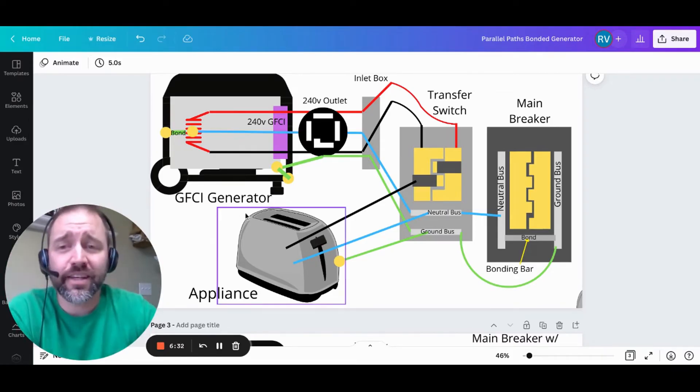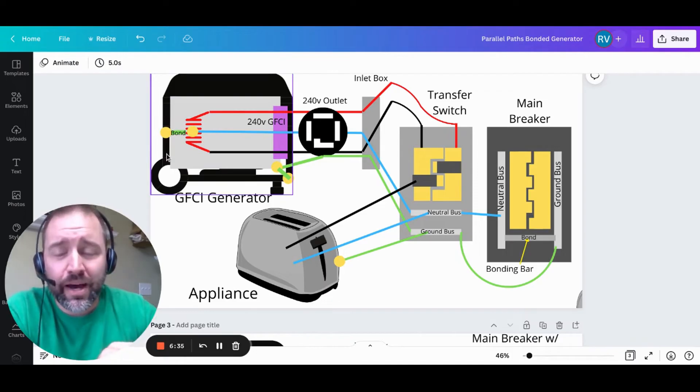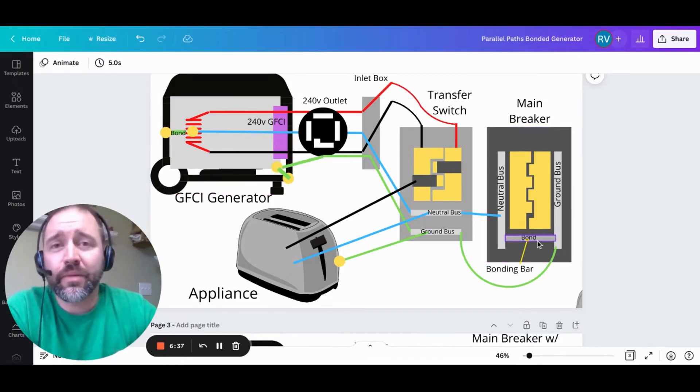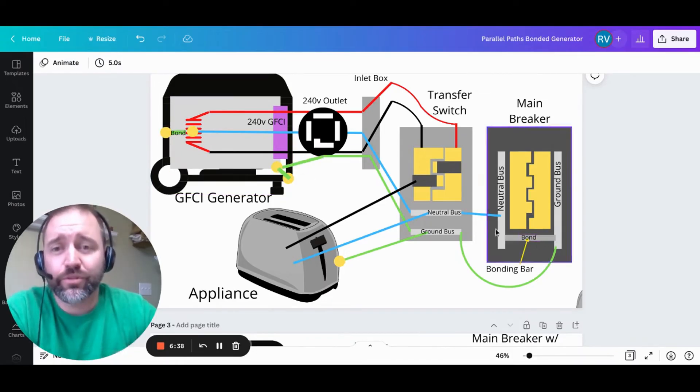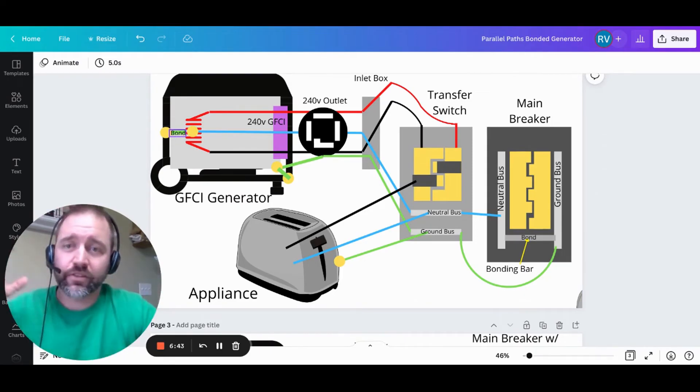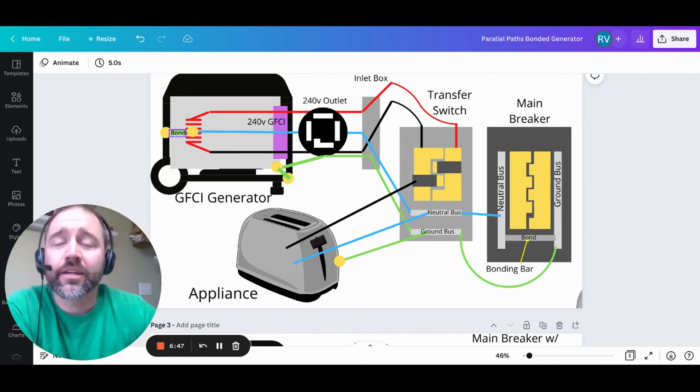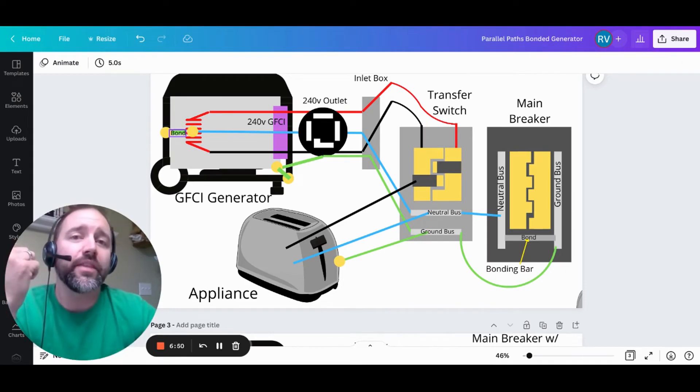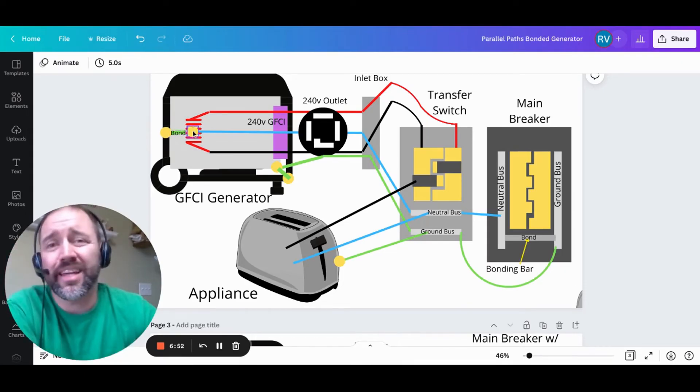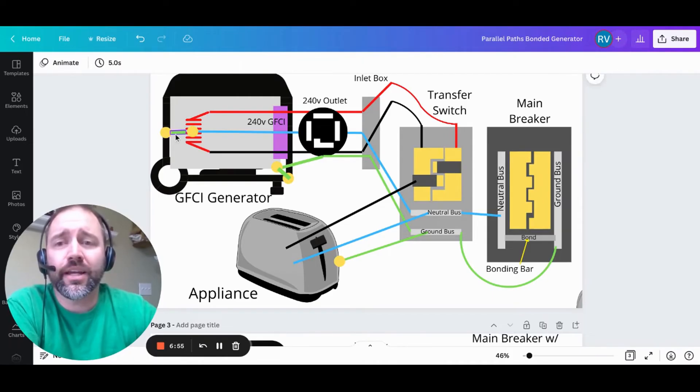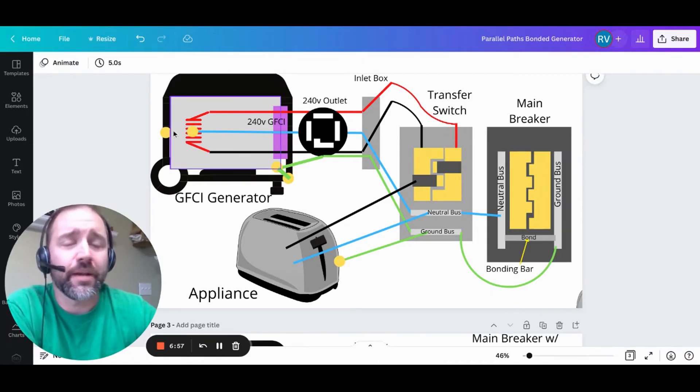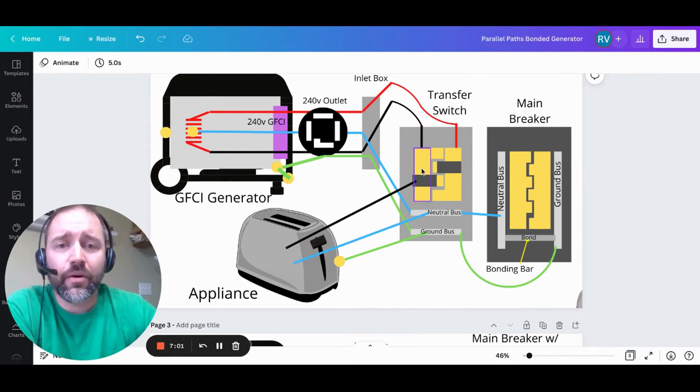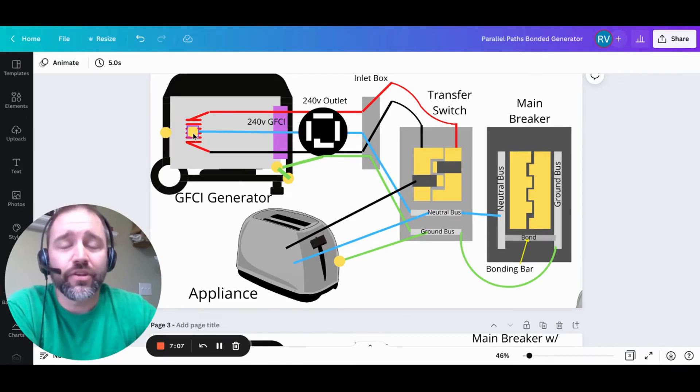How do we fix this? Basically, you have to get rid of one of the bonds. And I don't recommend doing it in the house. So the easiest way is to just remove the bond from the generator. Like I said, it's usually under the alternator cap. You just remove the jumper, and that'll take care of it. Consult with your manufacturer of your generator and the manual, and it'll probably say in there what you need to do. But let's take this out for a second and see what's going on. So now we have the electricity that leaves, comes down, does work, comes up the neutral, and it all has to flow back on the neutral in this particular case.